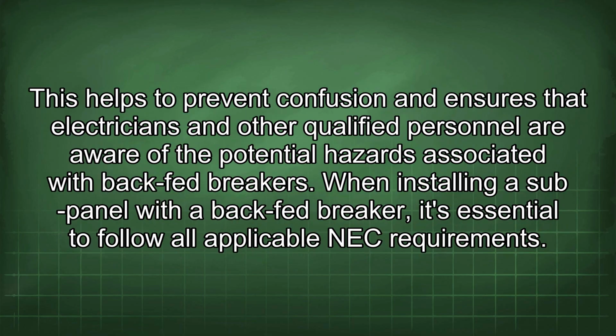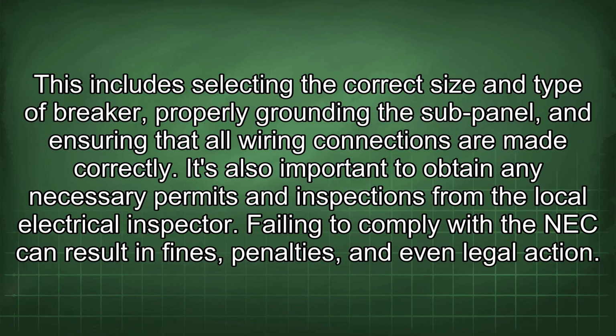This helps to prevent confusion and ensures that electricians and other qualified personnel are aware of the potential hazards associated with backfed breakers. When installing a subpanel with a backfed breaker, it's essential to follow all applicable NEC requirements. This includes selecting the correct size and type of breaker, properly grounding the subpanel, and ensuring that all wiring connections are made correctly. It's also important to obtain any necessary permits and inspections from the local electrical inspector.